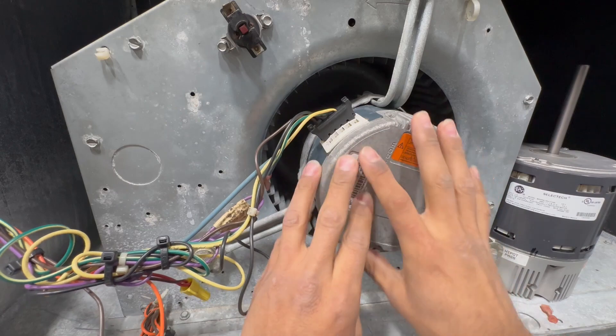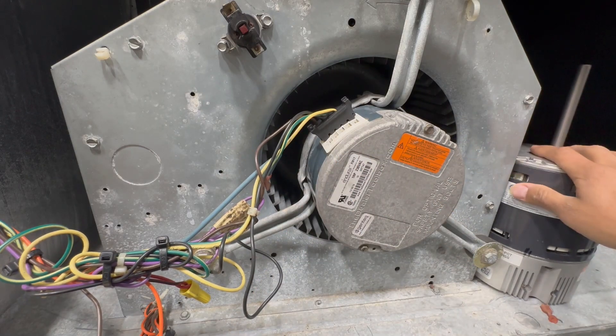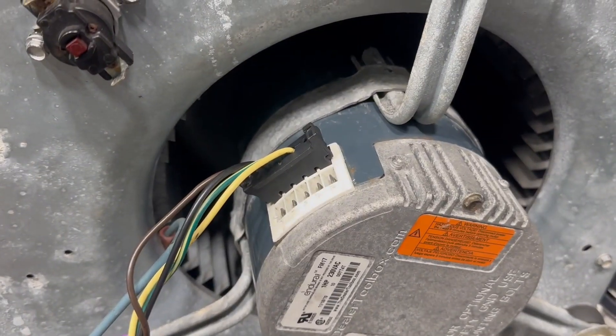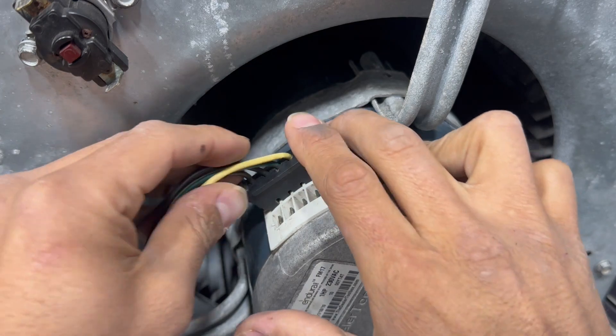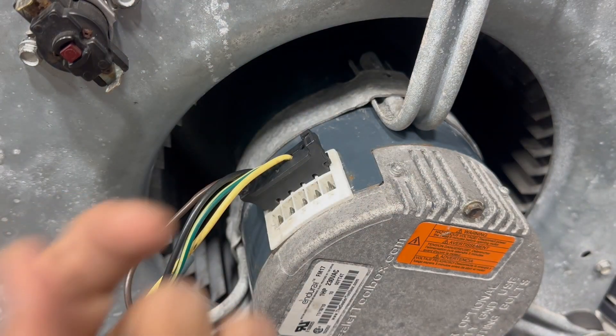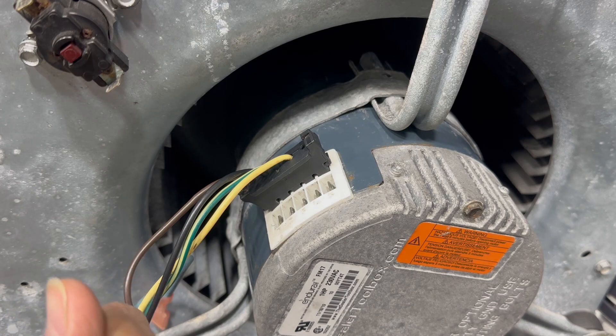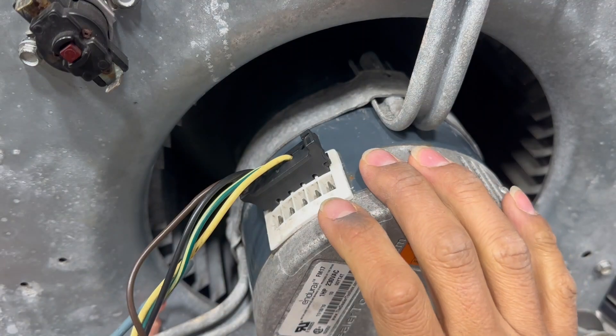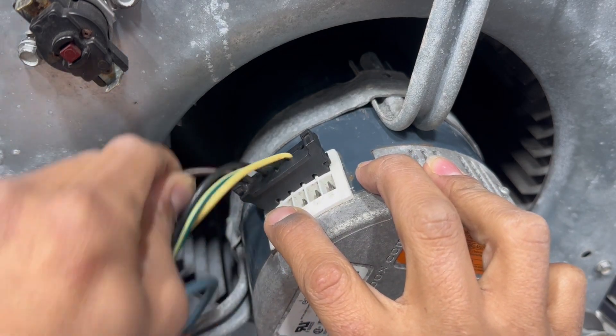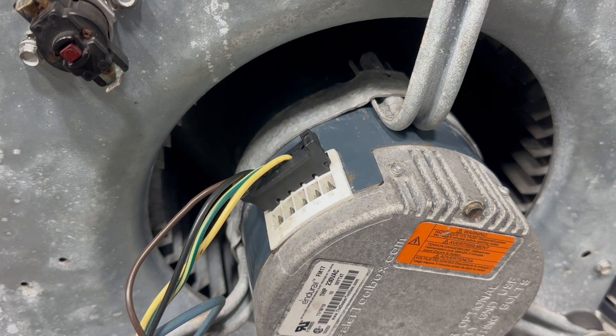Don't let ECM motors intimidate you. Simply put: high voltage is always present; low voltage on one of the numbered terminals is what turns it on. Never unplug the high-voltage connector with power on — turn off power, pull the connector, confirm voltage, put it back in with power off, then turn power on. Your 24-volt common is on the low-voltage side. Maintaining good airflow is the simplest way to extend the life of an ECM motor.